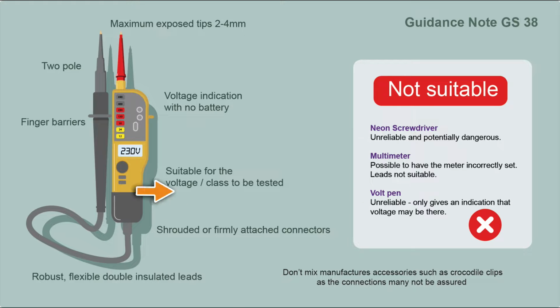So your voltage tester should be two-pole because you're measuring between two points to get a proper voltage reading. It should give a voltage indication even if there's no battery in it. You should have finger barriers on the probe so your hands don't slip down. It's got to be suitable for the voltage and class that you're going to be testing. The lead should be robust, flexible, double insulated, and the connection of the lead should be shrouded or firmly attached. And the maximum amount of exposed tip should be 2 millimeters. They say between 2 and 4, but 2 is the preferred amount.